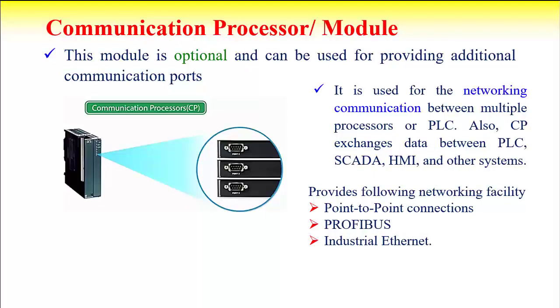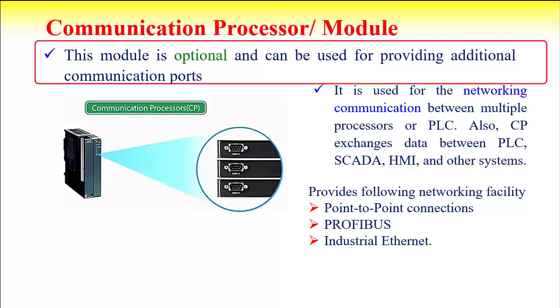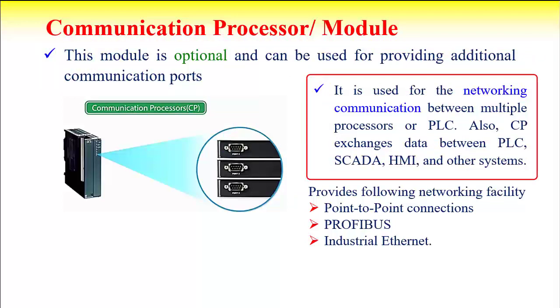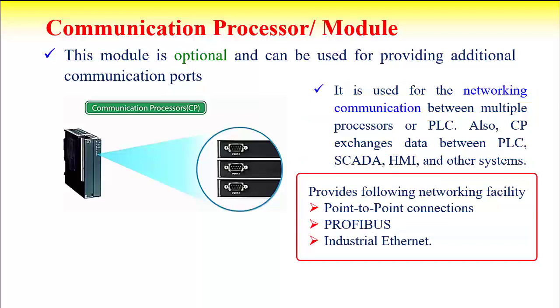The communication processor or communication module is optional — used only when required. These modules provide additional communication ports to communicate with different racks, remote I/O systems, or other systems. It is used for networking communication between multiple processors for the PLC, and also exchanges data between the PLC, SCADA, human machine interface, and other systems. This communication module provides different networking facilities like point-to-point communications, PROFIBUS communications, industrial Ethernet communications, etc.